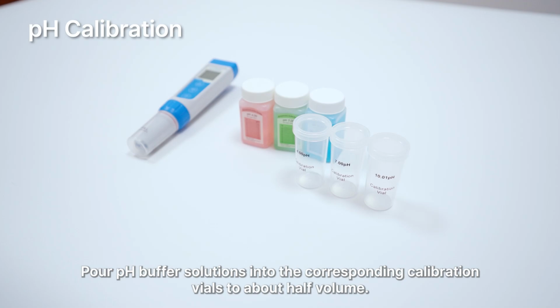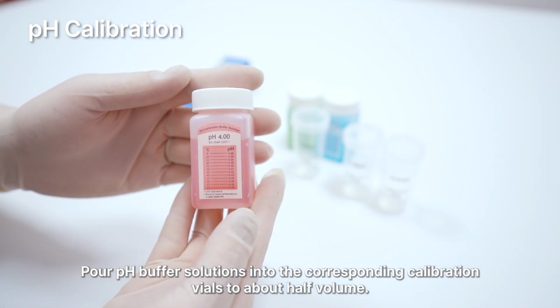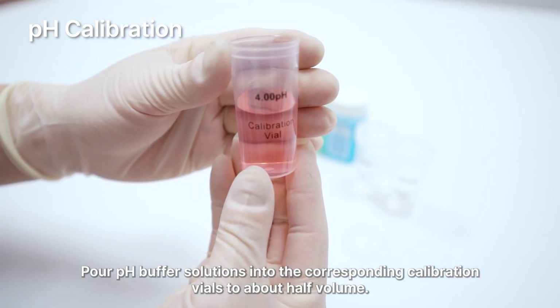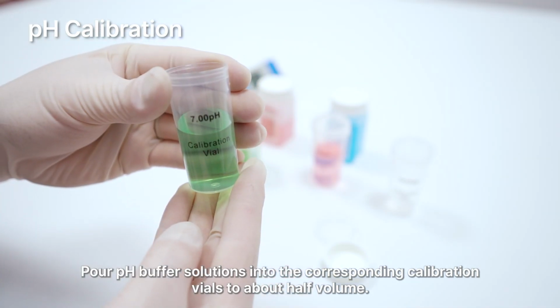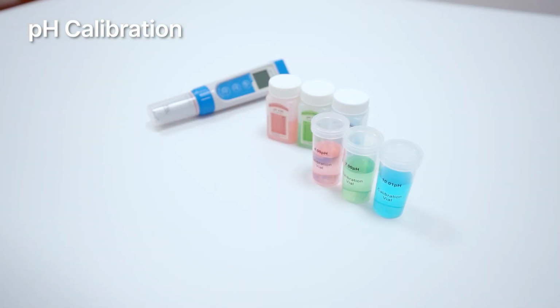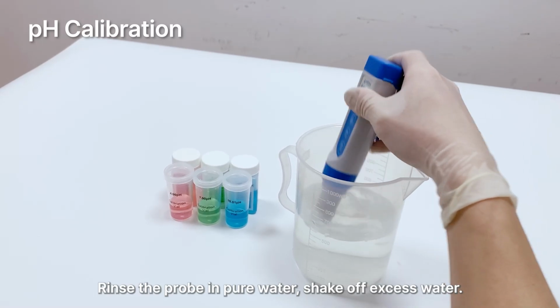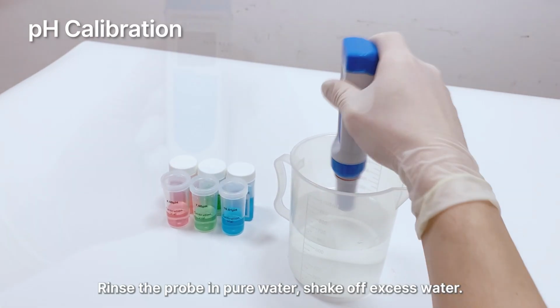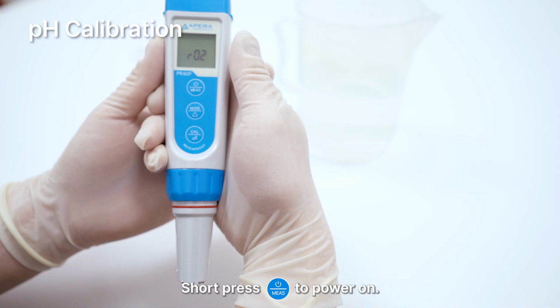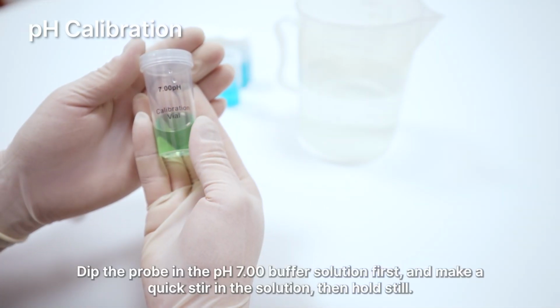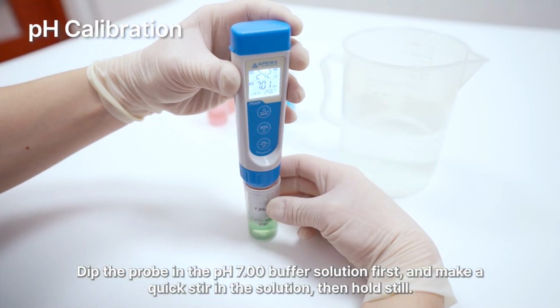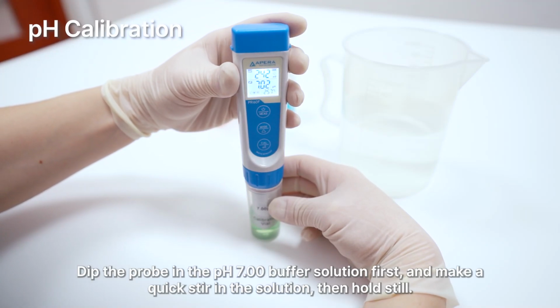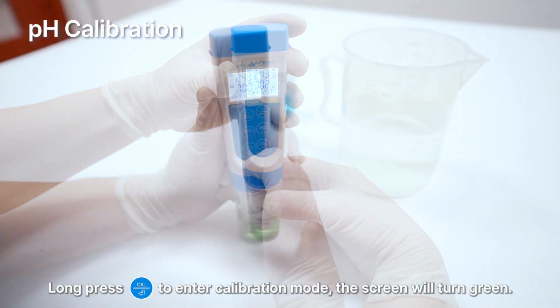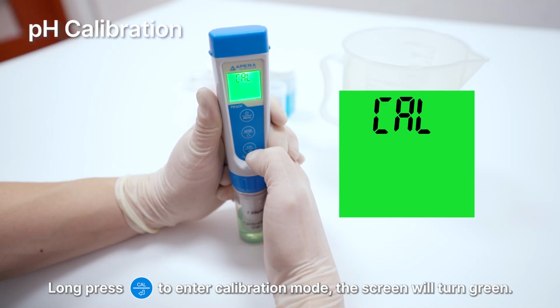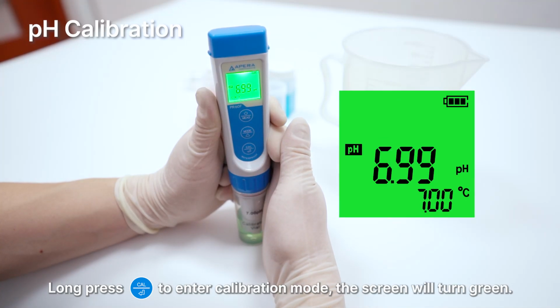pH calibration. Pour pH buffer solutions into the corresponding calibration vials to about half volume. Rinse the probe in pure water, shake off excess water. Short press to power on. Dip the probe in the pH 7.00 buffer solution first, and make a quick stir in the solution, then hold still. Long press Cal button to enter calibration mode, the screen will turn green.